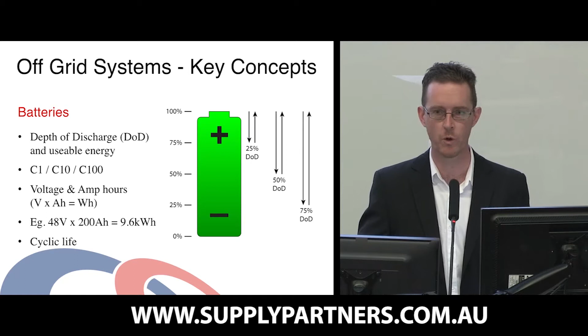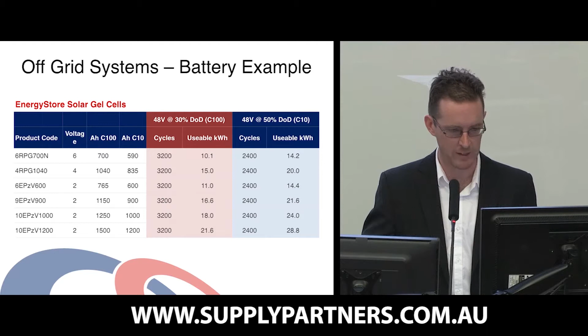Here's just a quick example. You can see if you have a 48-volt battery and discharge it over 100 hours, you're going to get a certain number of usable kilowatt hours. If you discharge at 50%, discharging it more, then you will get more energy out of it, but the cyclic life reduces because you're working the battery harder.